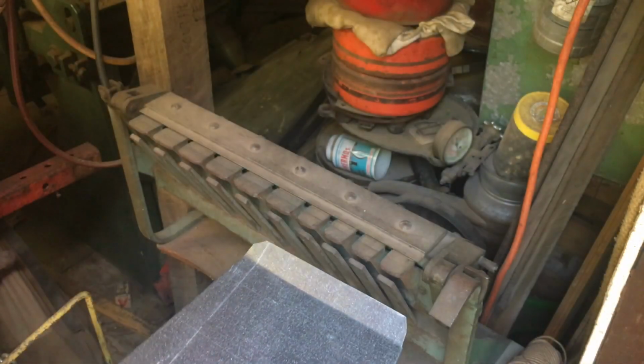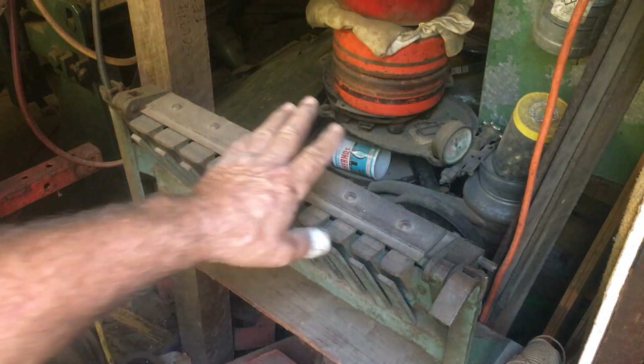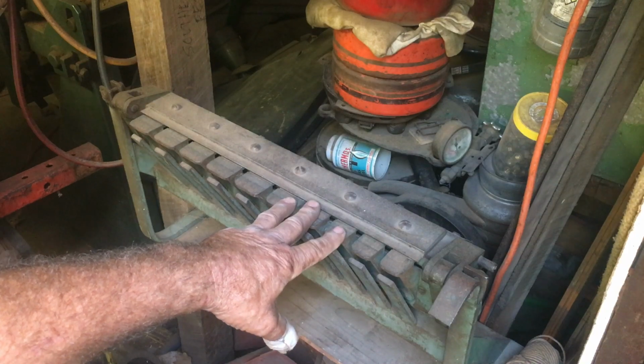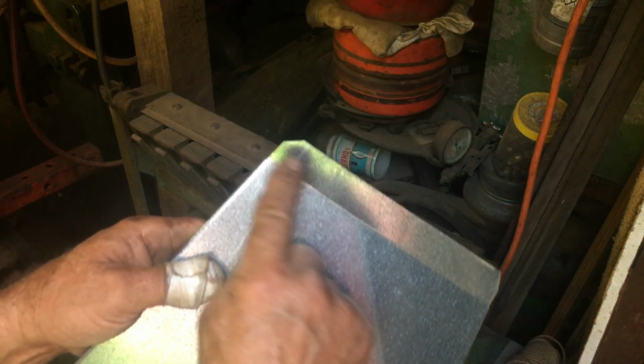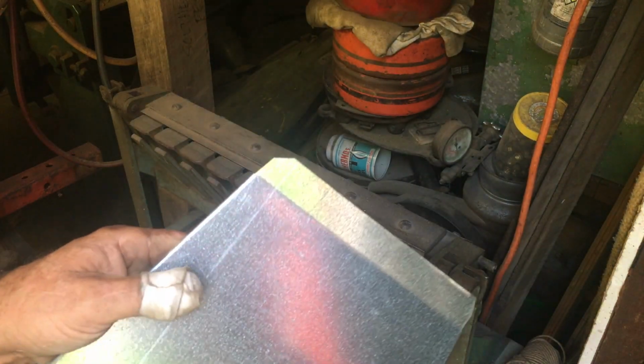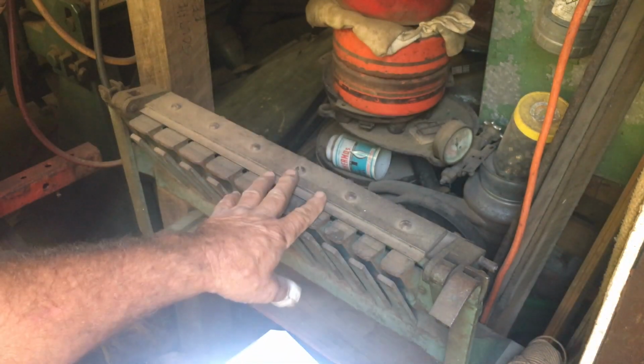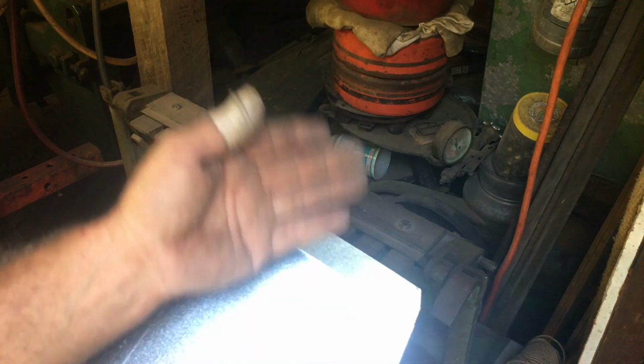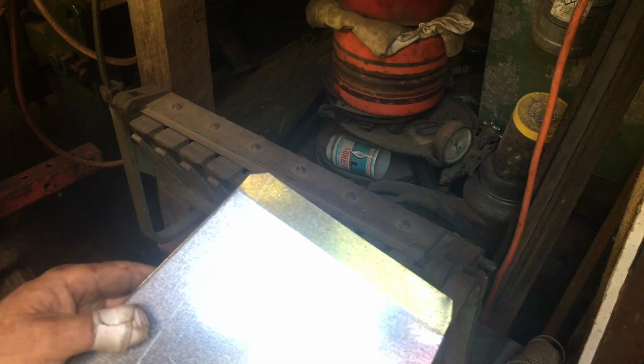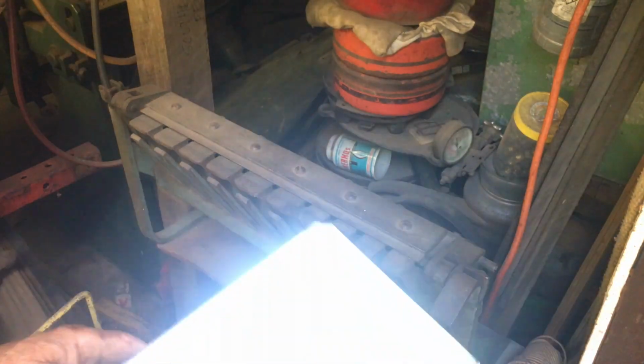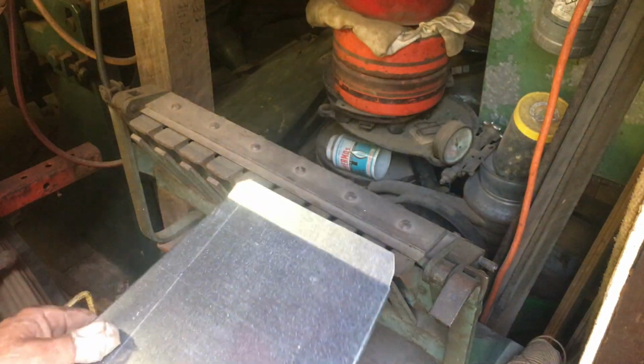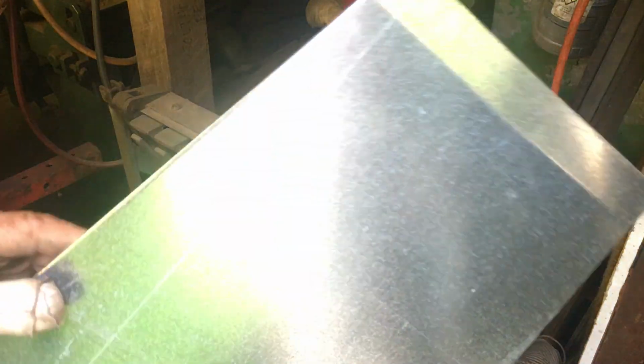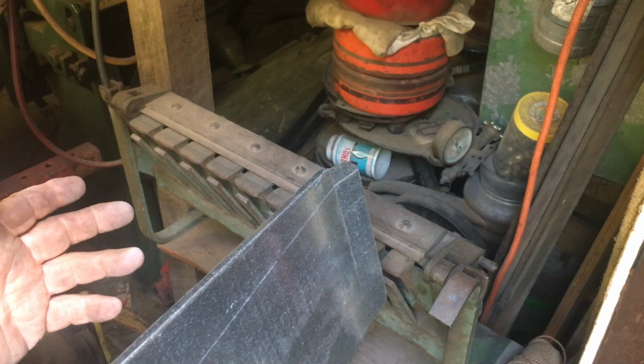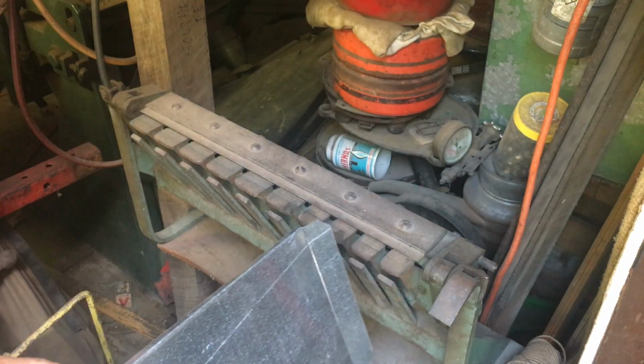Okay, now bear in mind, this particular machine here is called a Cleat Bender. The things you attach ductwork together with are called drive cleats. So this Cleat Bender is going to make a 1/2 inch reasonably perfect 180-degree bend on that without distorting the rest of the piece of metal. You can put that drive cleat on in individual pieces like this, or wait till the whole assembly is assembled and then just do the two portions.